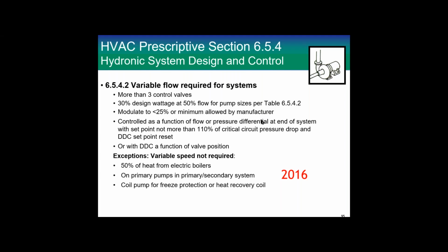We haven't found anything other than a vane axial fan that would work like that on a fan, but for pumps there are some other things. But anyway, with the cost of variable speed drives, there's probably no debate. Modulate to 25% or minimum allowed by the manufacturer. So the pump goes down that far if it can. Controlled as a function of flow or pressure differential at the end of the system with a set point not more than 110% of critical circuit pressure drop and DDC set point reset.